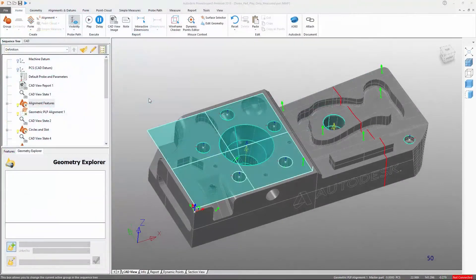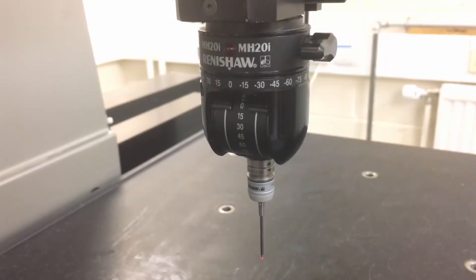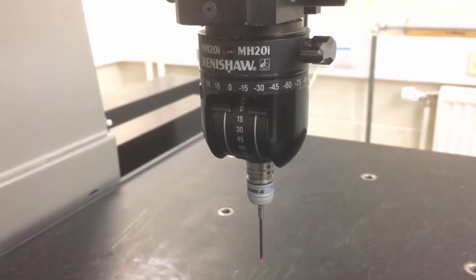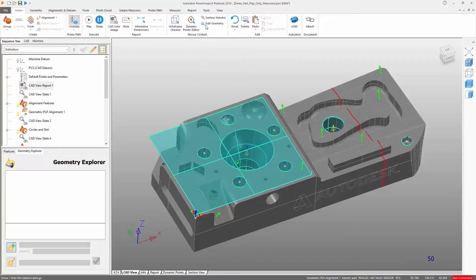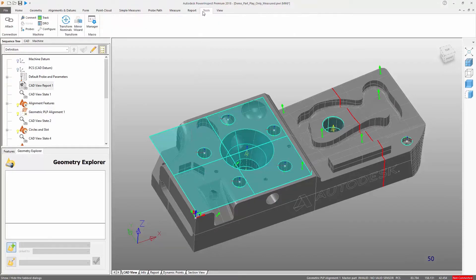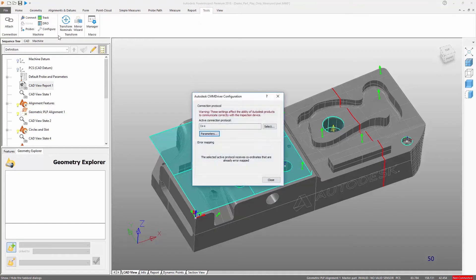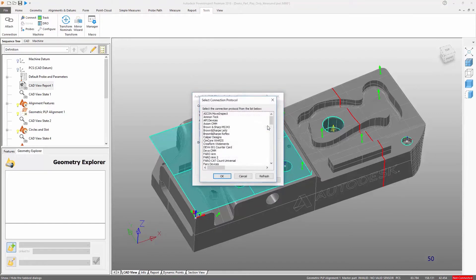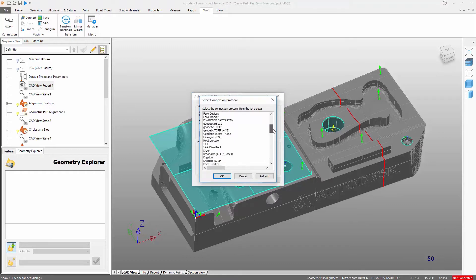This inspection sequence has been created to be measured with a manual CMM. To connect PowerInspect to the device, first make sure the device is turned on and is connected to the PC. Then navigate to the Tools tab and click the Configure option. Here we choose the correct protocol for the device.